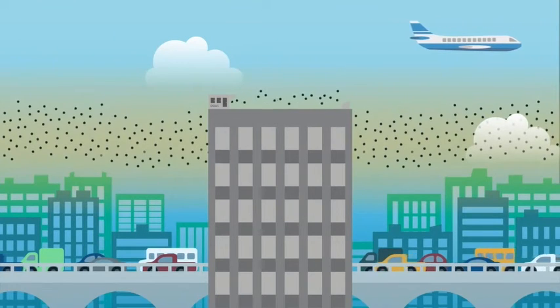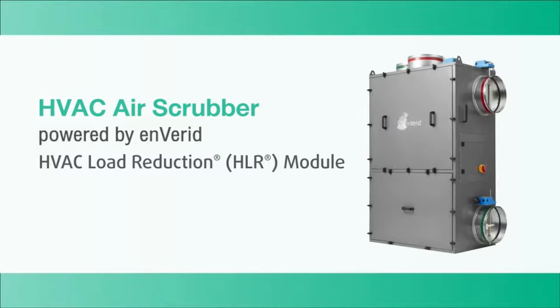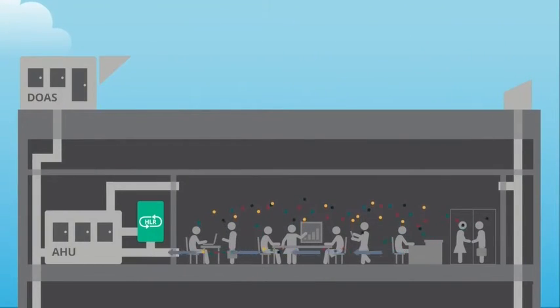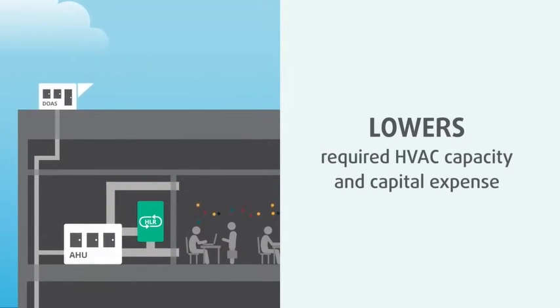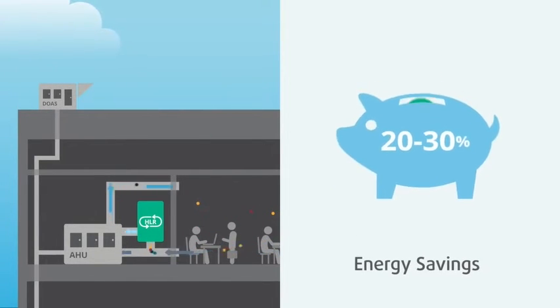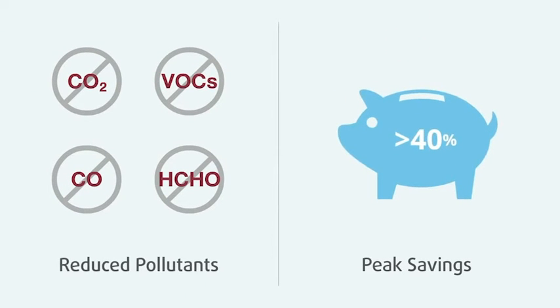Especially for buildings in cities or near highways. You can solve these problems with the enVerid HVAC Load Reduction, or HLR module. HLR technology is the only solution that safely removes all indoor air contaminants through molecular cleaning, which improves indoor air quality and reduces the need for outside air by 60 to 80%. This lowers required HVAC capacity for heating and cooling and capital expense, while reducing annual energy consumption by 20 to 30%, with peak savings of over 40%, and much less outdoor pollution brought into the building.